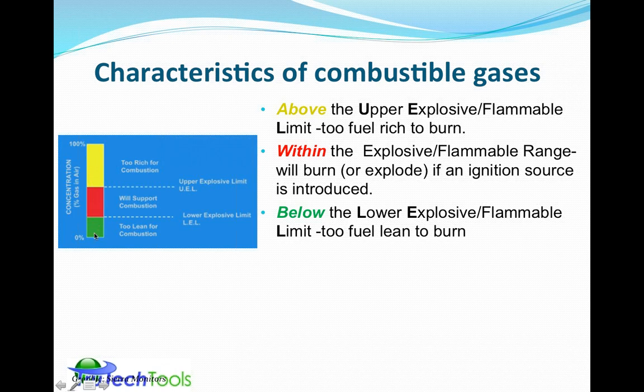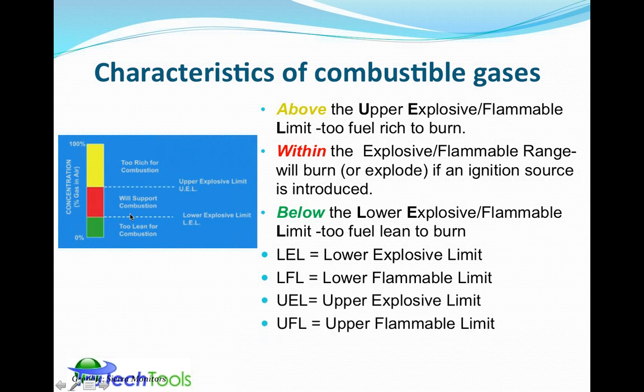Something to pay attention to here: we've got green, yellow, and red lights stacked up a little differently than you would see at a traffic intersection. Green at the bottom is too lean for combustion, but red is the zone where it will support combustion, will support explosion. It's yellow up here above the upper explosive limit, because as soon as this concentration drops back down and there's enough air or oxygen present, it will move into the zone that supports combustion. So this is not a safe area by any means because it can rapidly change into a combustible zone. So LFL and LEL basically mean the same thing: lower explosive limit, lower flammable limit, and the same thing with the UEL and UFL.